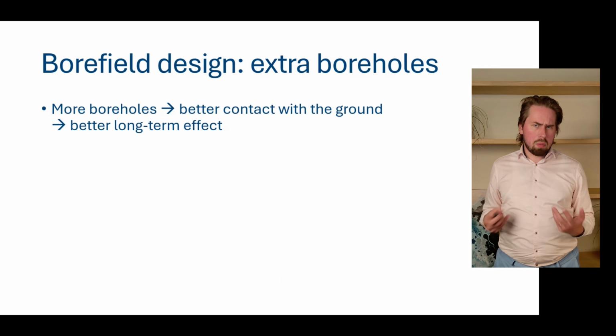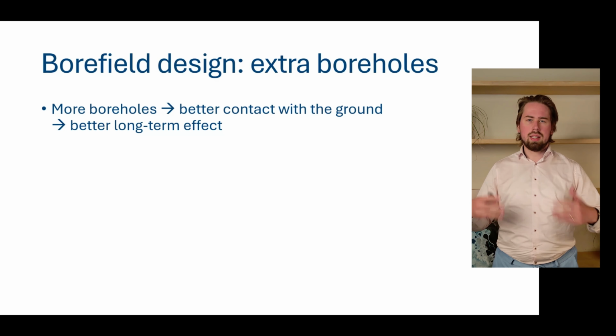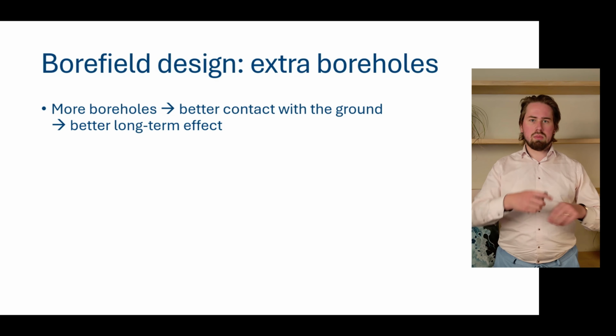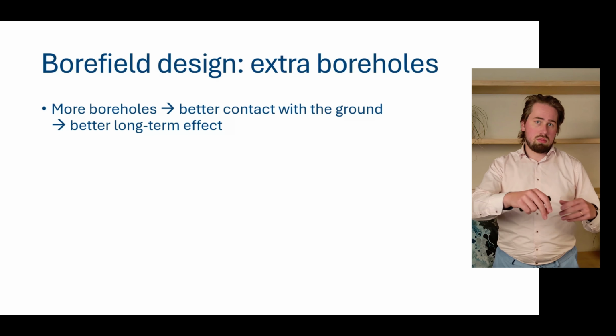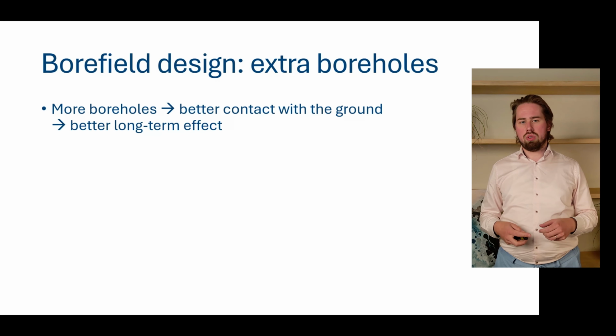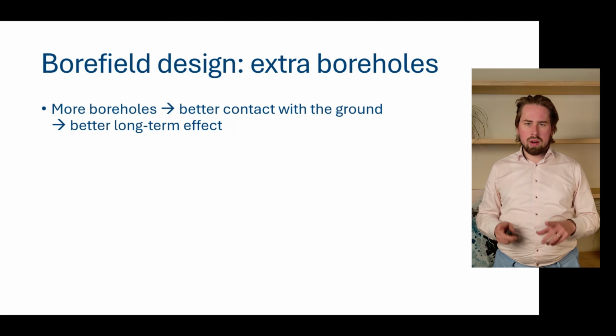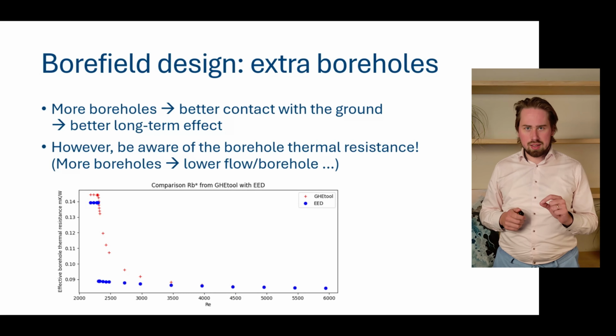Now, another common practice solution is just to say, okay, we have a certain imbalance, let's drill extra boreholes. Because the more boreholes we have, the more room we have to exchange heat with the ground, and again, this is better for the long-term effect. And in general, this is true. However, we need to account for a certain thing, and that's the borehole resistance.